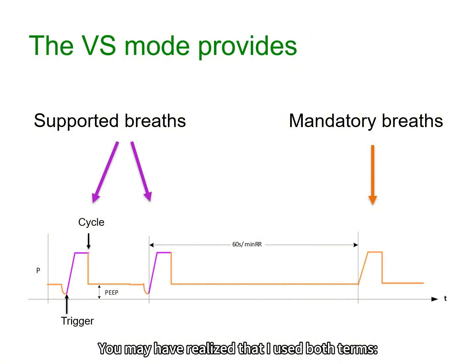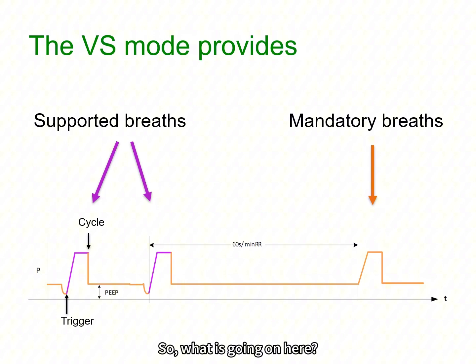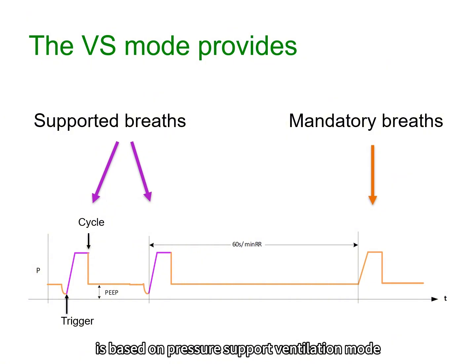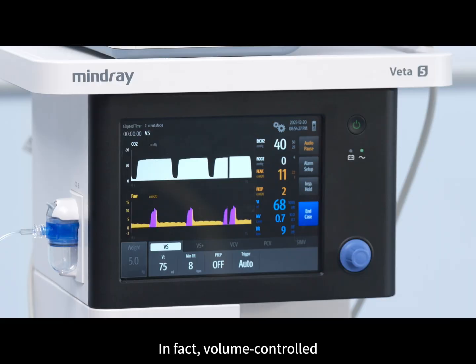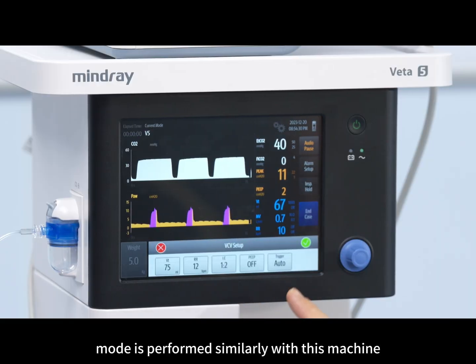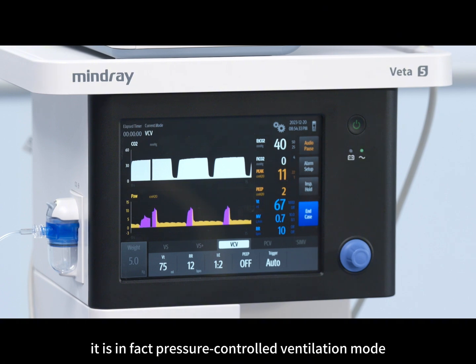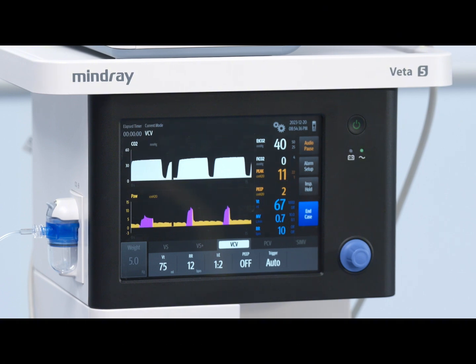You may have realized that I used both terms for pressure and volume support. So what is going on here? In fact, the Veta 5 machine is based on pressure support ventilation mode. The ventilator starts with an estimated pressure support, then measures the resulting tidal volume and modifies the pressure support to reach the desired tidal volume at next breath. In fact, volume-controlled ventilation mode is performed similarly with this machine. It is in fact pressure-controlled ventilation mode, with the pressures being continuously adjusted to reach the desired tidal volume.